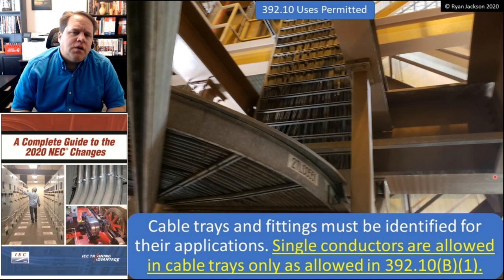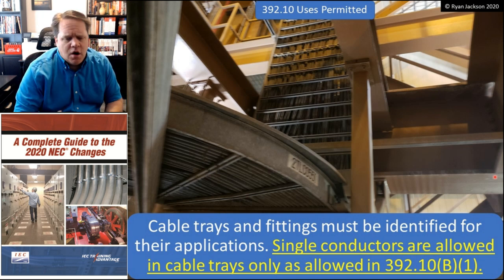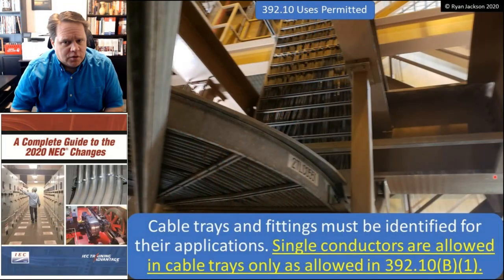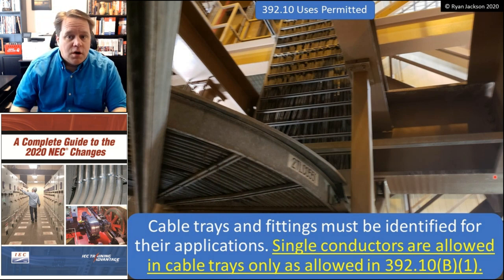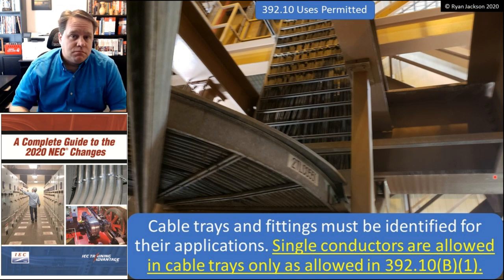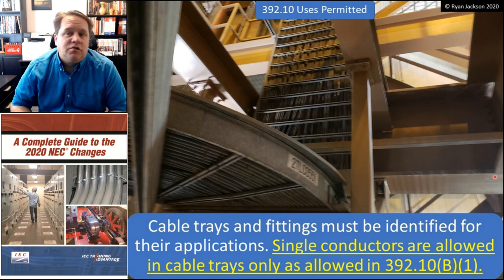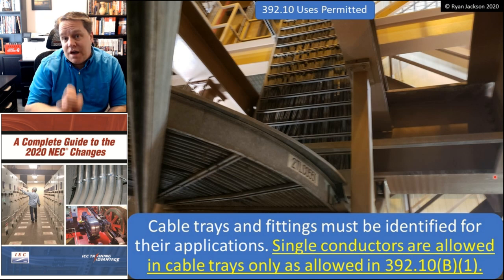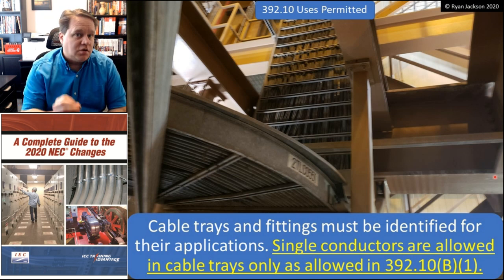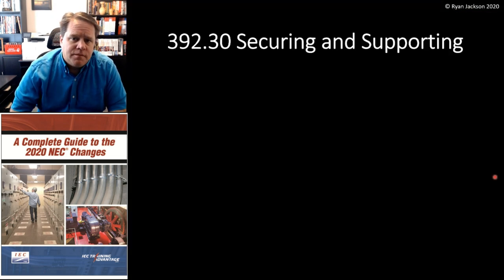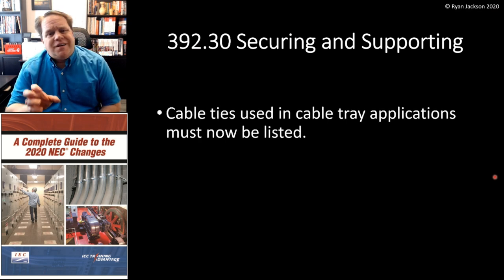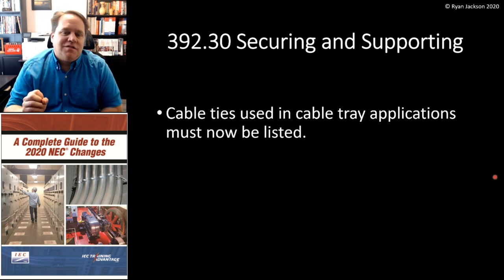Single conductors are allowed in cable trays only as permitted in 392.10(B)(1). This is saying that if you're in a supervised industrial location and you have conductors that are 1/0 AWG and larger — at least for circuit conductors — and they're rated for cable tray usage, then you can put individual conductors in your cable tray. This is only for supervised industrial installations; you can't do that in a house or a commercial building.